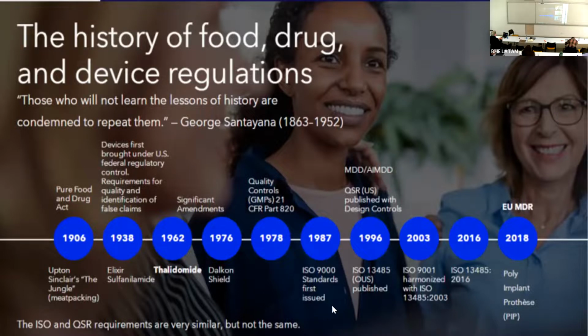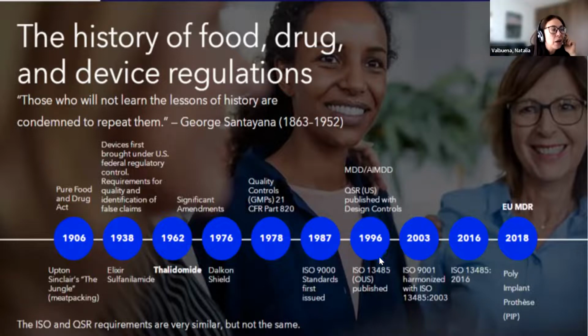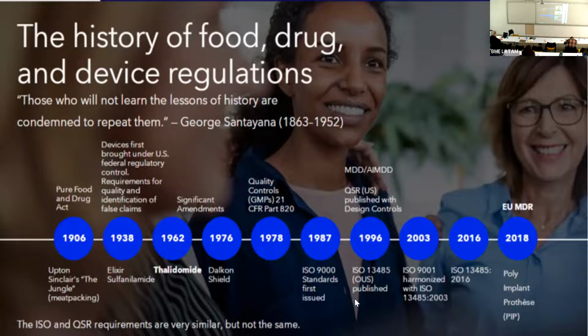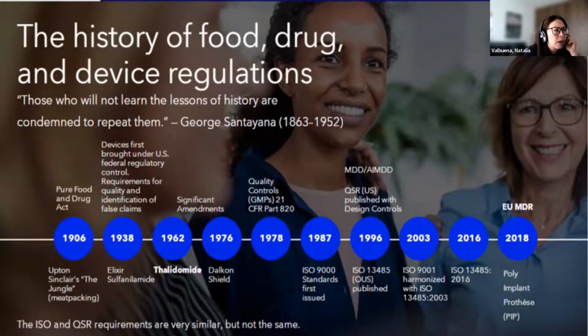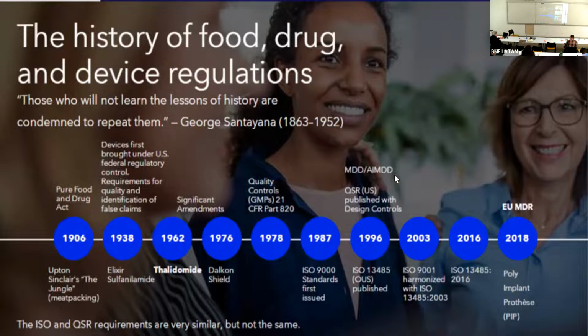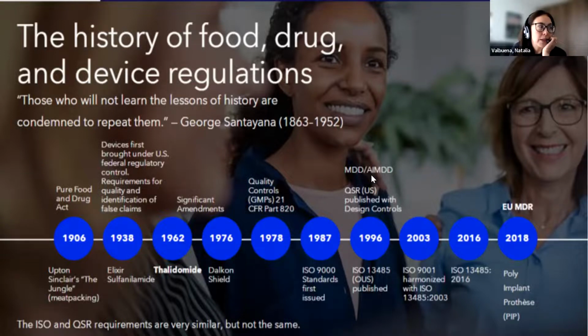And here starts the meaning of quality system regulation and requirements. In 1996, we start to hear about ISO 13485, sorry for my English. It was published, and it is the first quality system regulation dedicated to medical devices. Also at that time, the regulation in Europe for medical devices was created, that means MDD and AIMDD, Medical Device Directive and Active Implantable Medical Device Directive. This is the regulation that was applicable in Europe until 2018.